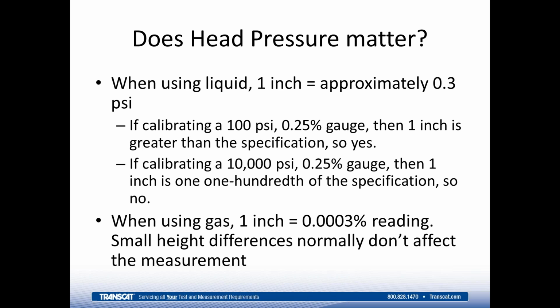So the key takeaway when it comes to head pressure is for many applications, it's not going to be a major impact if you're working with relatively low accuracy devices. But the easiest way to handle it is to make sure that your reference and test are relatively close to the same vertical height, and that with low pressure, working with a liquid media, oil or water, then it's going to be much more of an impact. So it helps if you're using gas for very low pressure or low pressure and oil or water for higher pressure, because then your head heights become less of an impact.